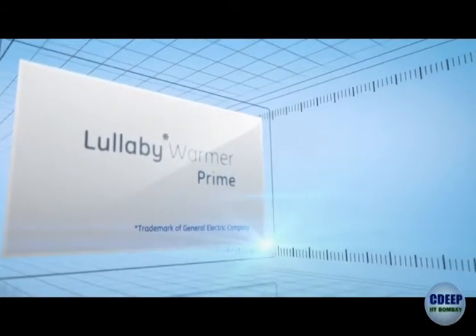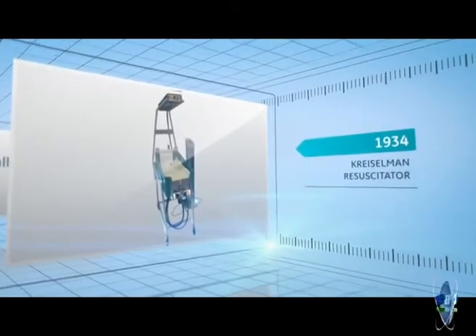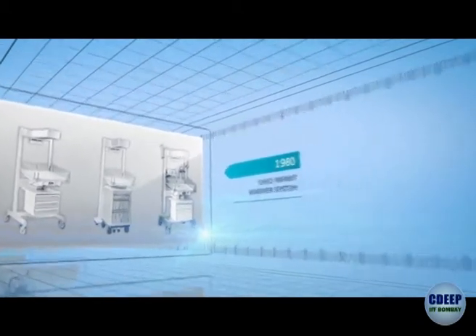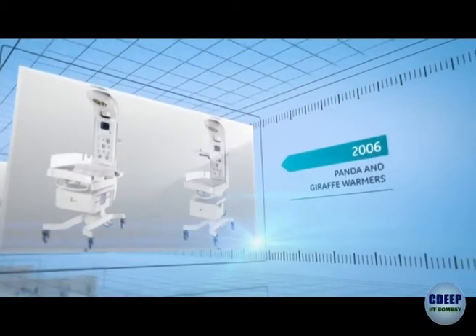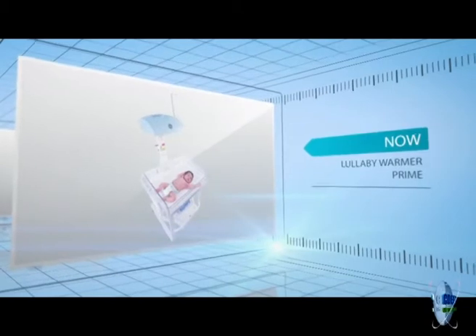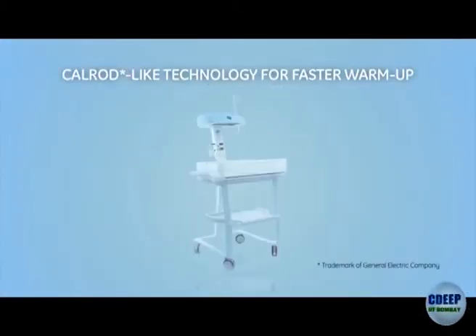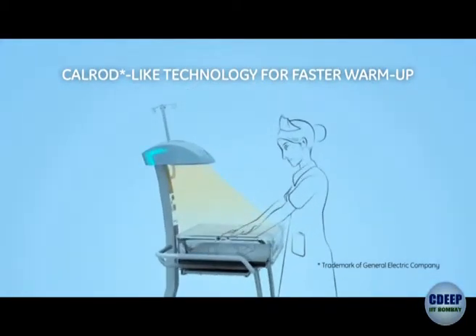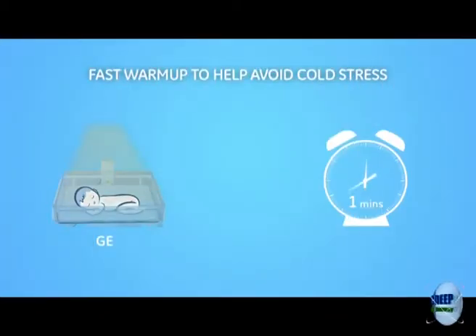Introducing the Lullaby Warmer Prime from the company with 80 years of experience with infant warmers. GE's latest innovation has been redesigned from the ground up to efficiently deliver exceptional thermoregulation at a fantastic total cost of ownership. One of the many features that distinguishes the Lullaby Warmer Prime from other warmers is its patented J-profile recessed heater design that directs heat evenly to the bed for more patient thermal stability. In addition, it is equipped with a cartridge CalRod-like technology heater that can reach near maximum irradiance in just 4 minutes.